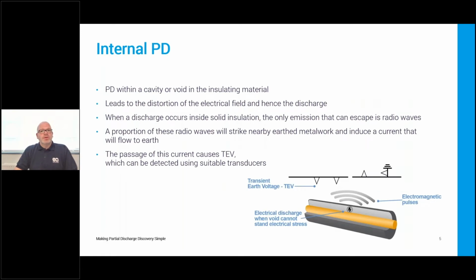If we look a little bit more at internal PD, a term that I'm sure many of you have come across, and we at EA use it a lot, is TEV, or transient earth voltage. When we turn up to do a survey, or yourselves, if you're using an UltraTEV, for example, checking the assets, what you're looking for is TEV. And remember, this refers to internal PD only.